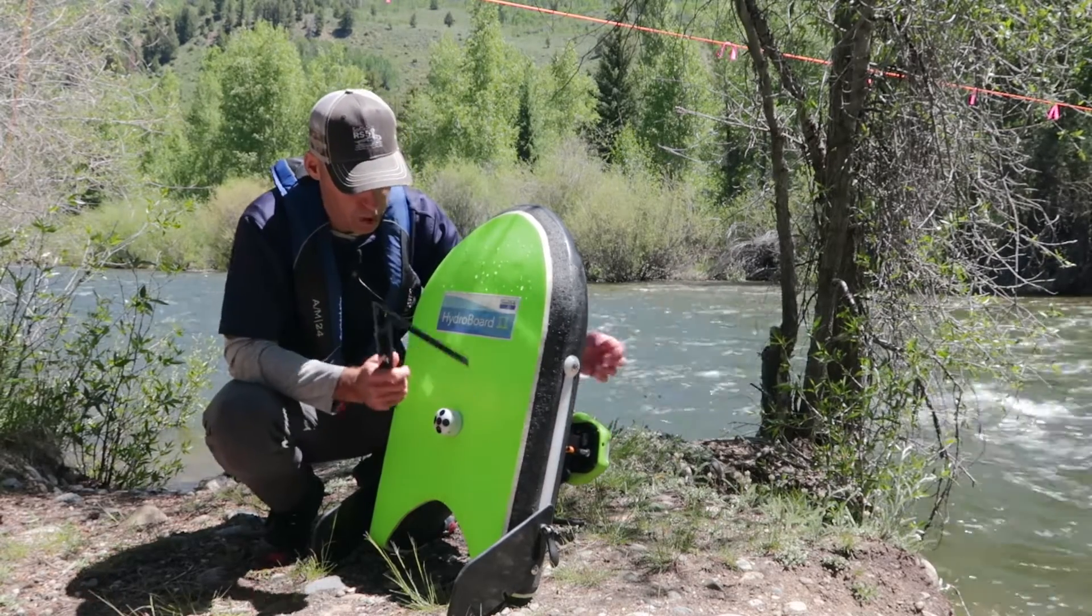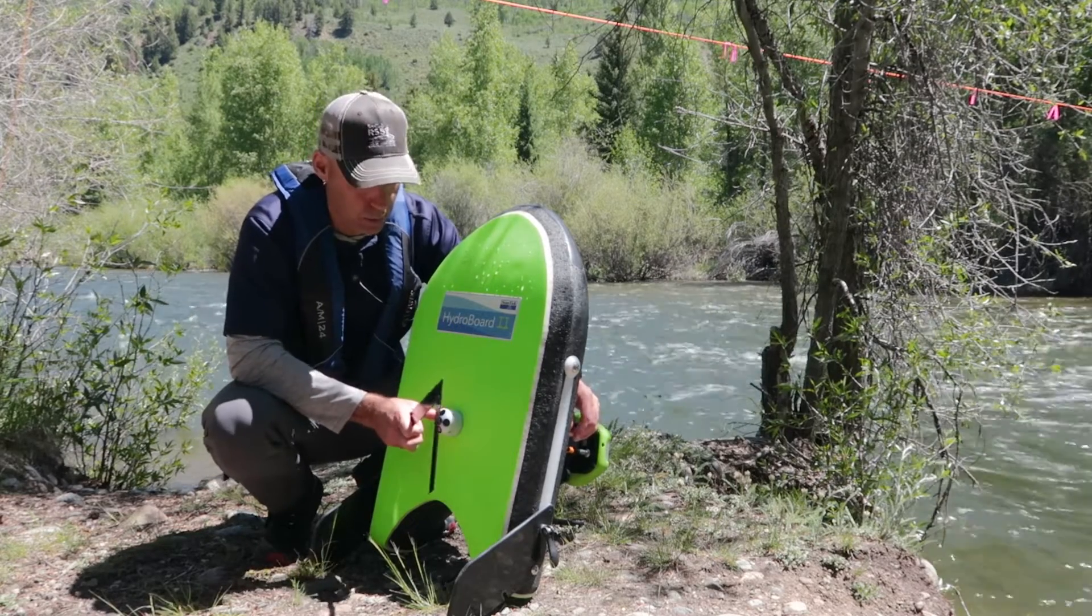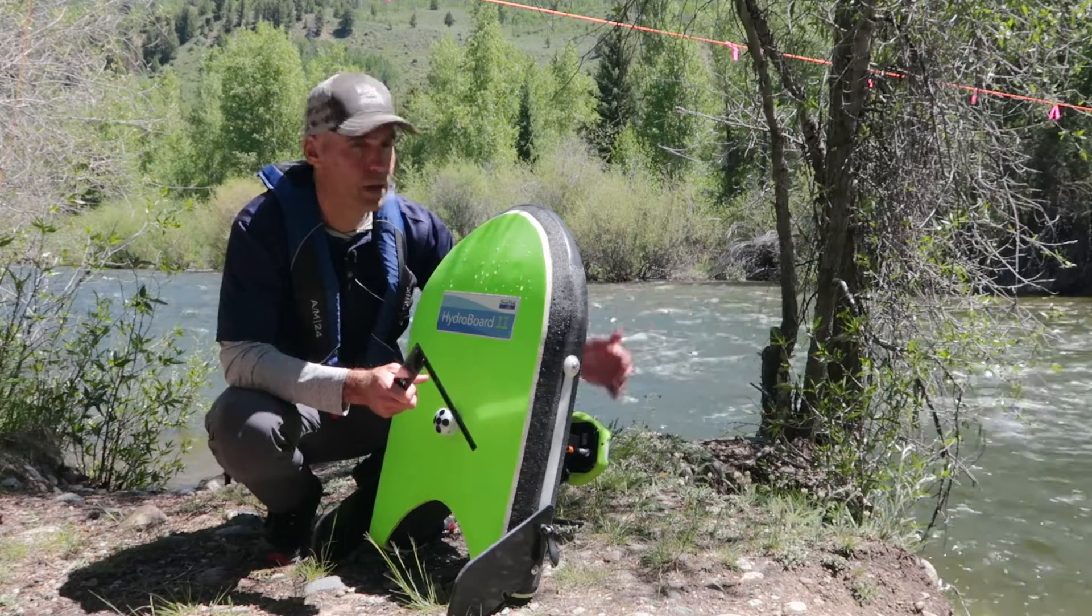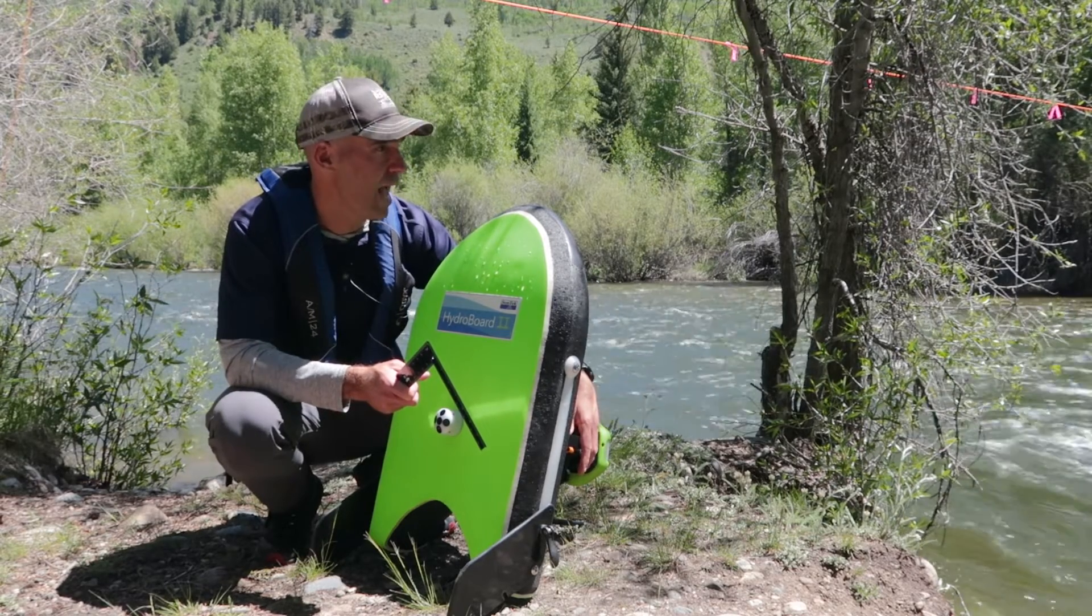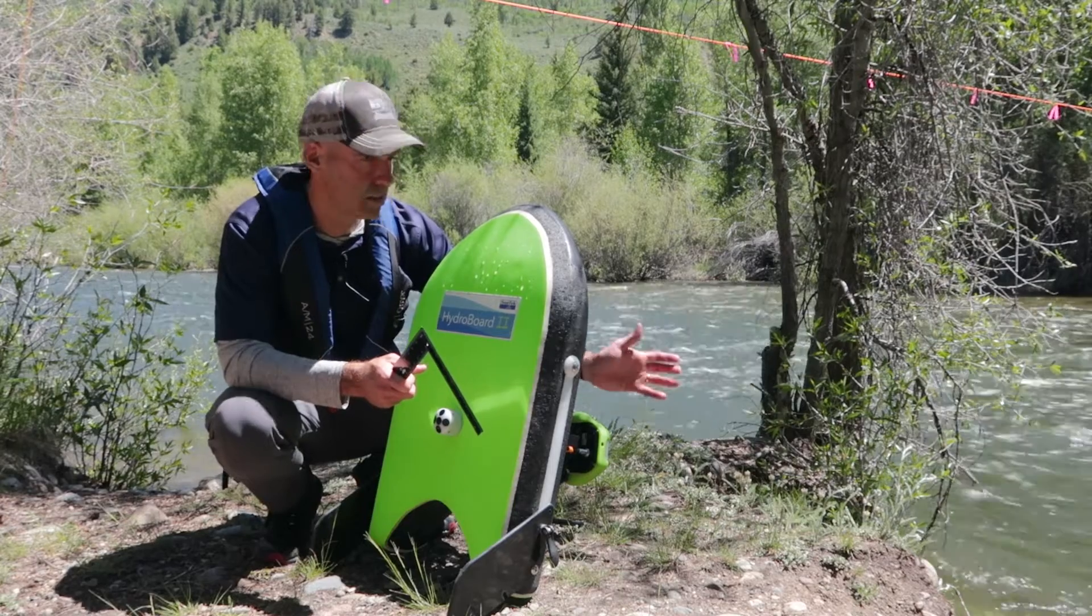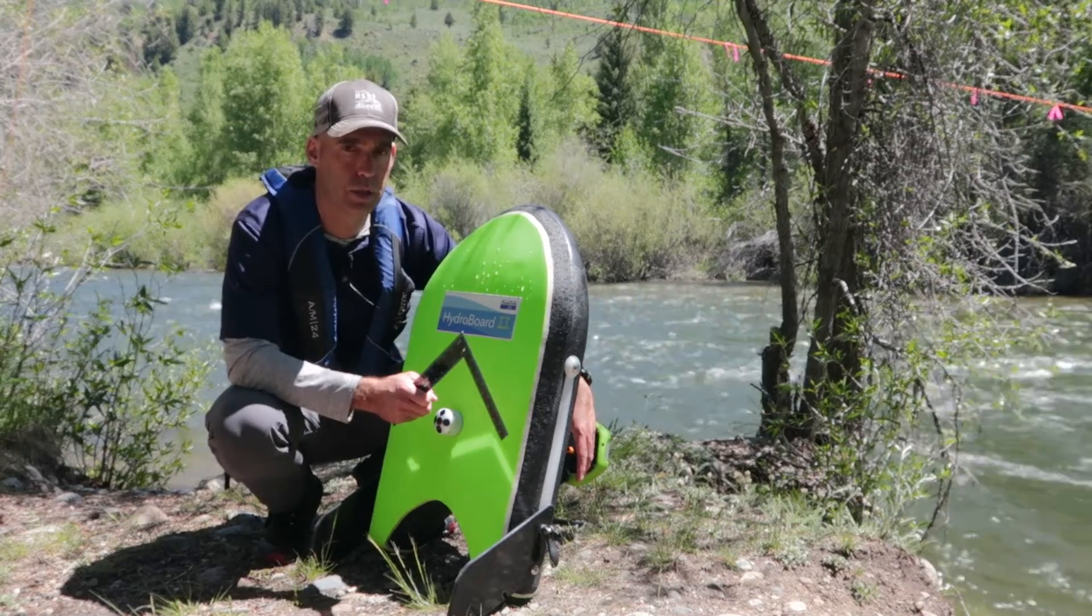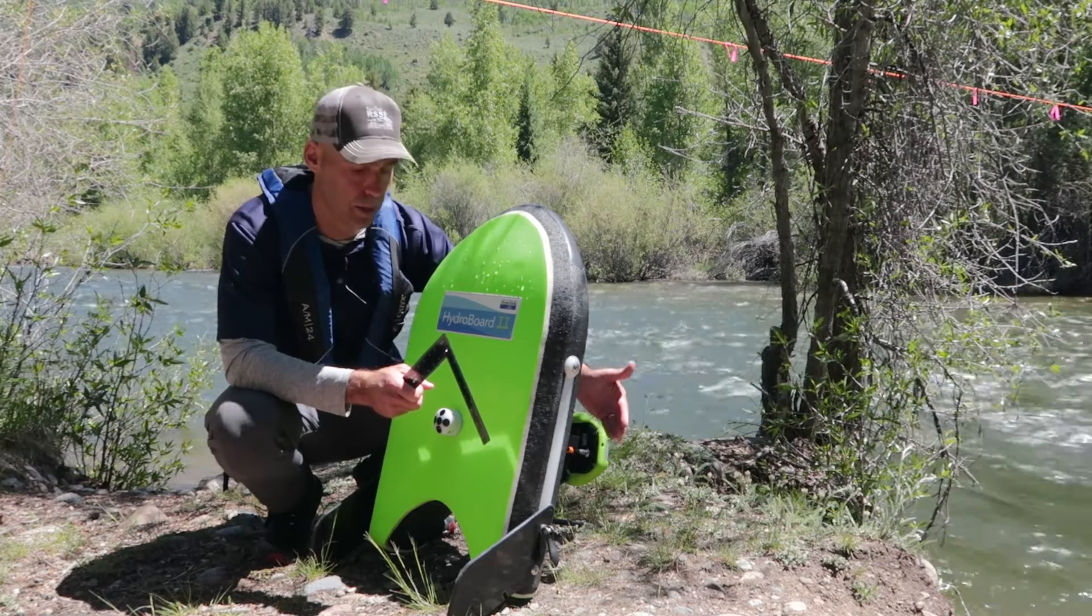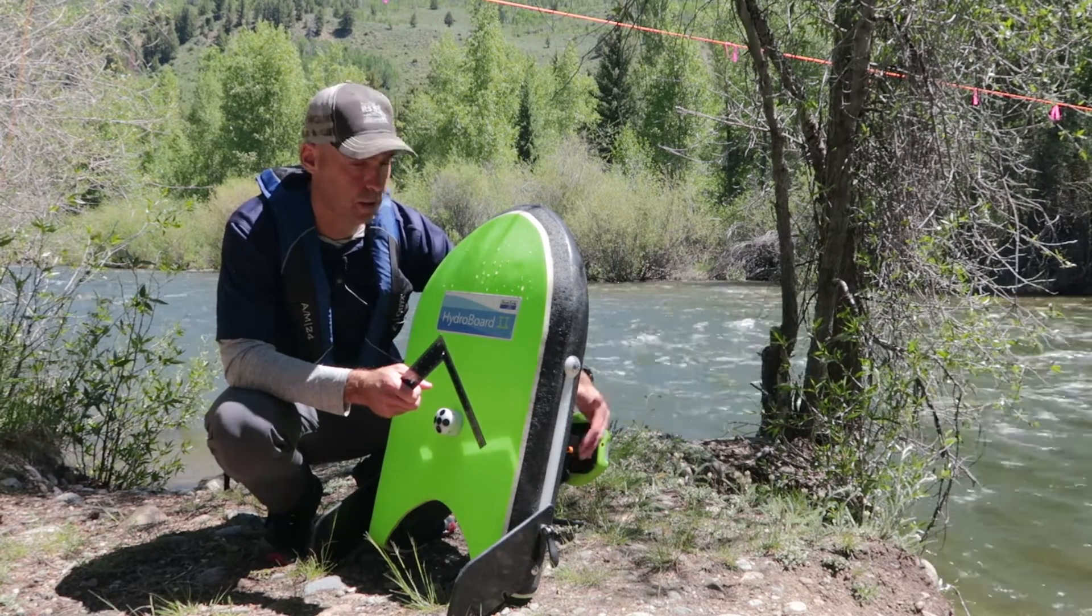We're operating today with the transducer pushed as far down as we can get it, because as you'll see behind me, we're at the Blue River near Breckenridge, Colorado, and it's in high flow. So this is the best site we could find, but it's somewhat turbulent. There's some standing waves and we do not want the transducer to come out of the water because the transducer needs to stay submerged to make a good measurement.